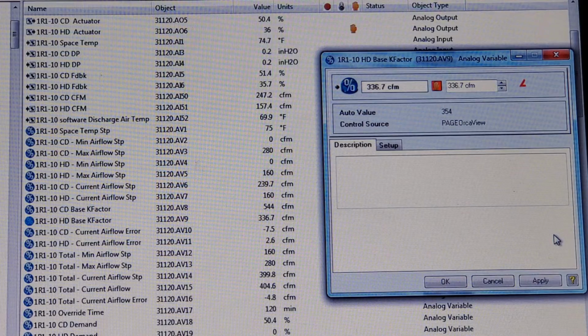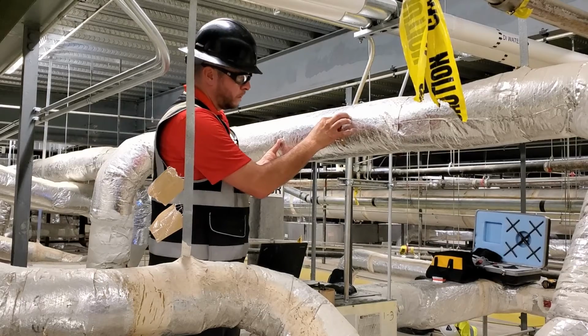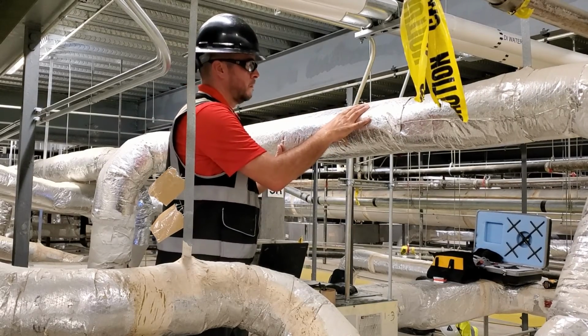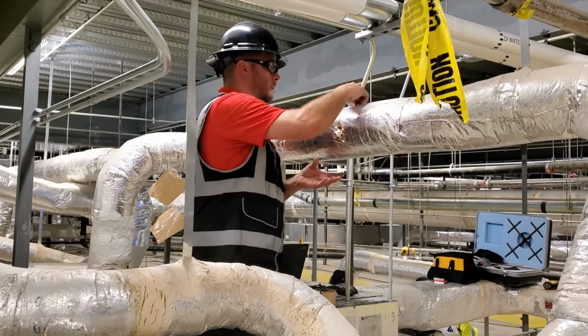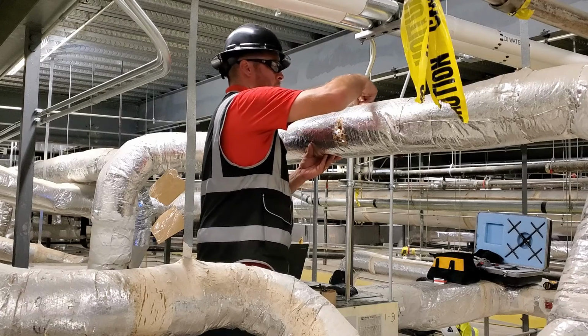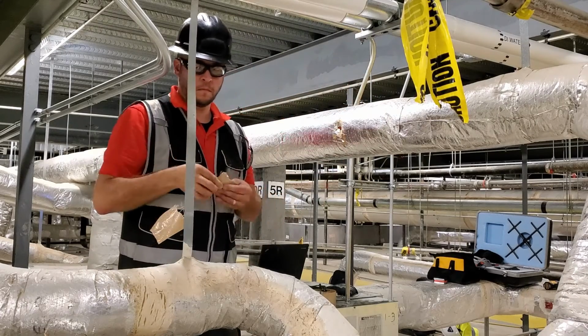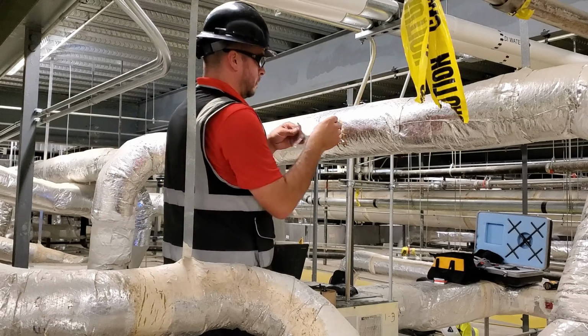And once it gets there, then you can double check your reading by either utilizing a static. In this case, we can't. You can utilize a velocity though, and then, to confirm the flow, you can redo the traverse just to confirm that it did in fact calibrate and go to that CFM.